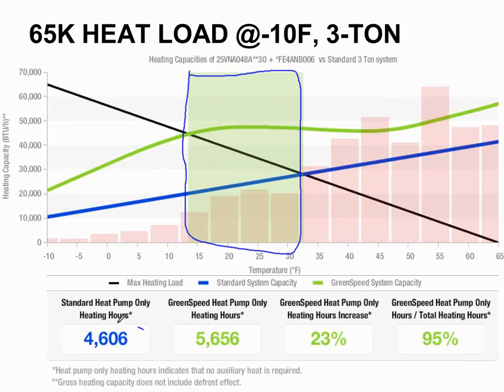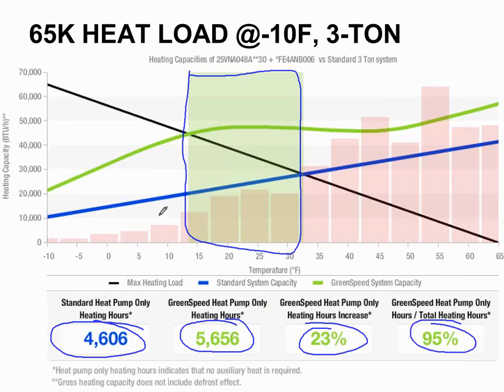And then it'll tell you, well, your standard system is going to run 4,600 hours in the heat pump mode, right? And if I do the variable speed one, it's going to run 5,600 hours. I'm getting 23% more runtime, and I'm covering 95% of the total outdoor temperature, and I'm only needing help from something else over here. So hopefully that makes some sense to everybody too.